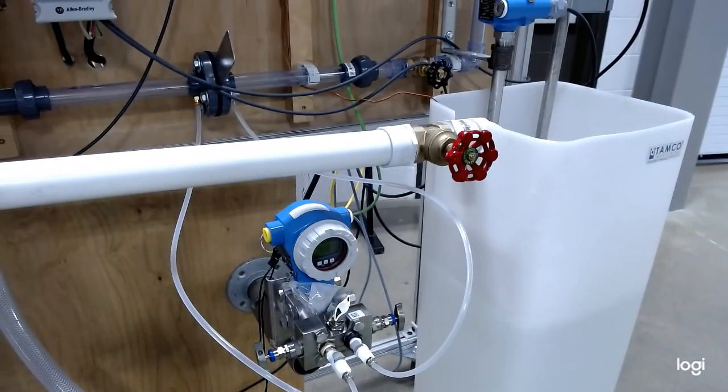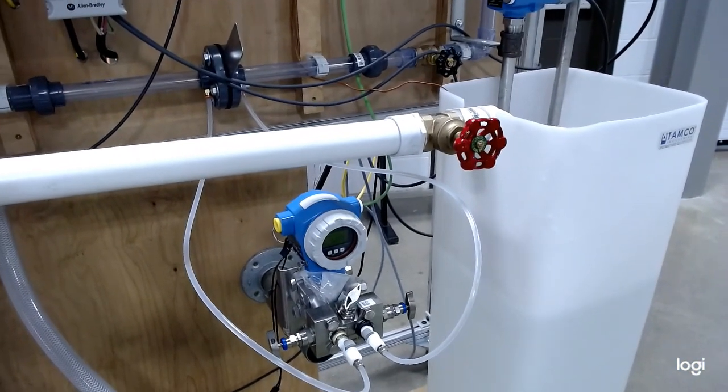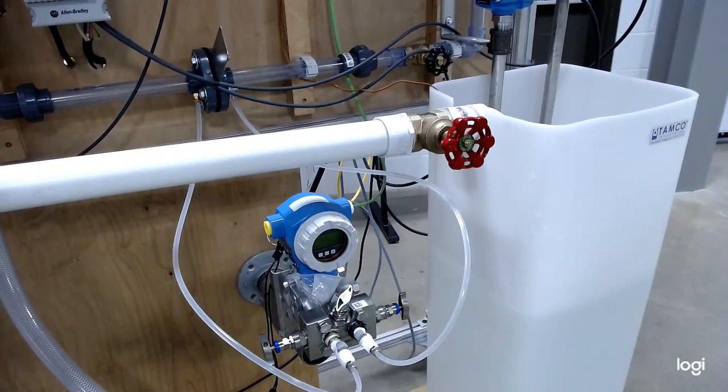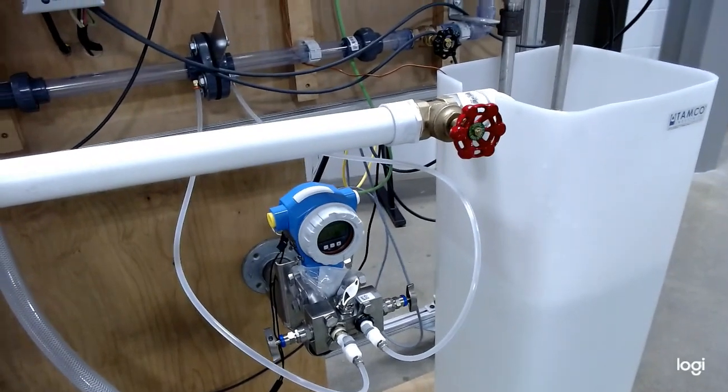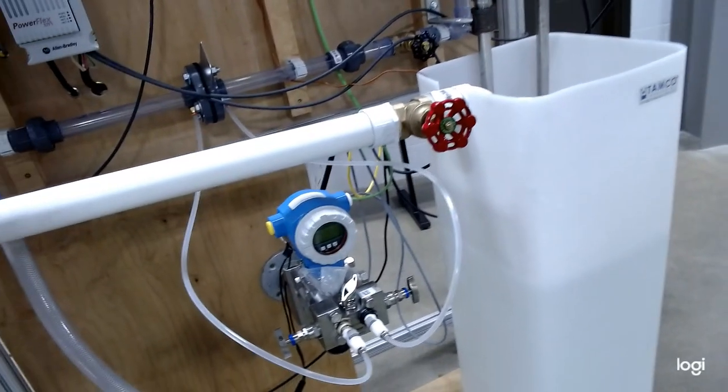To do that we actually needed to have water in the line. So we had the pump fired up and running and as there was pressure in this water line we went ahead and cracked open the bleeders on the back of the transmitter here.